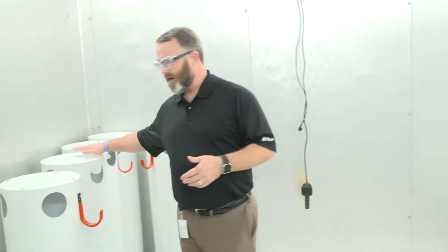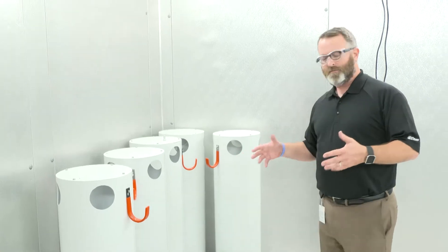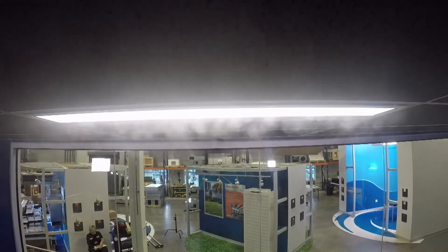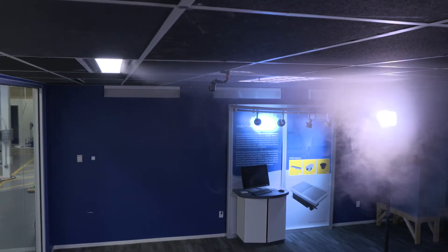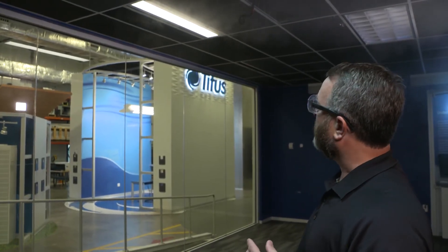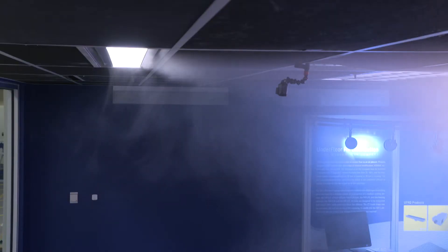One of the other things we have here is our heat dummies. What these dummies are meant to do is emulate people, so that we're constantly maintaining a set temperature inside the space. We're also trying to maintain temperature in here without producing any heat plumes that will affect the induction we see inside the chilled beam. We're going to be doing a smoke Isovel test on the Titus Luxe, making sure we're getting ceiling adherence from the air coming out of the unit. As we see the smoke, it's going to start generating in the air handler, come out of the air slot, and form a negative pocket right along the edge of the diffuser. As it does that, it pulls the smoke along the ceiling. You can see the air coming along and, as some of it starts to return with the smoke, it turns back, pulls back into the air stream, and gets carried down along the ceiling again. As it induces that air, we get a lot of turnover and, for that reason, a very consistent temperature throughout the entire space.